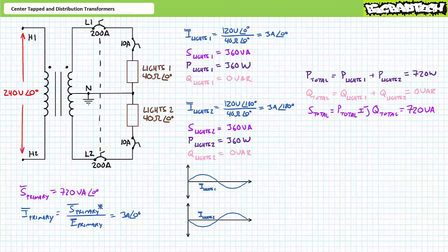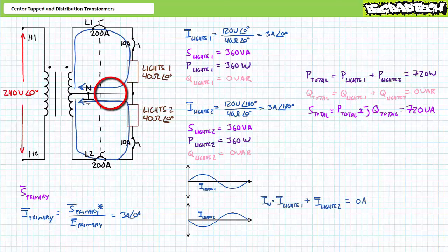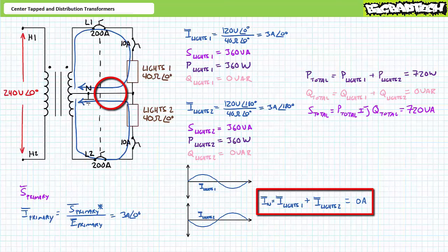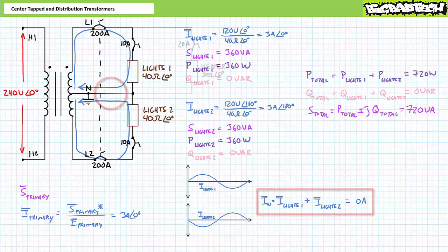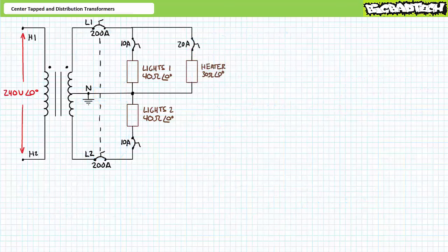It's helpful to remind ourselves that phasors are merely shorthand representations of sinusoidally oscillating conditions. At a given moment when 3 amps of current enters lighting load 1, 3 amps of current happens to be leaving lighting load 2. The return path afforded by the neutral line is the current in lighting 1 plus the current in lighting 2. Given currents in the lighting loads are equal in magnitude and out of phase with one another, current in the neutral line while in the balanced condition is 0 amps. This is true only in the balanced condition.